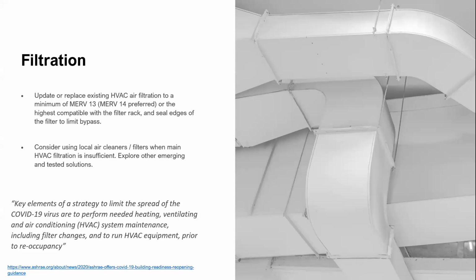Other emerging solutions are for the filters. We have electrostatic precipitators, which could replace MERV 13 and MERV 14 filters. They work by charging the particles and allowing them to stick to electronic plates so that you can just brush them off later. Another one is bipolar ionization, which is done through a device that generates positive and negative ions. The ions stick to the virus, which deactivates them. This is more preferred because it has a very low parasitic load and very low impact on the power consumption of the air handling units.